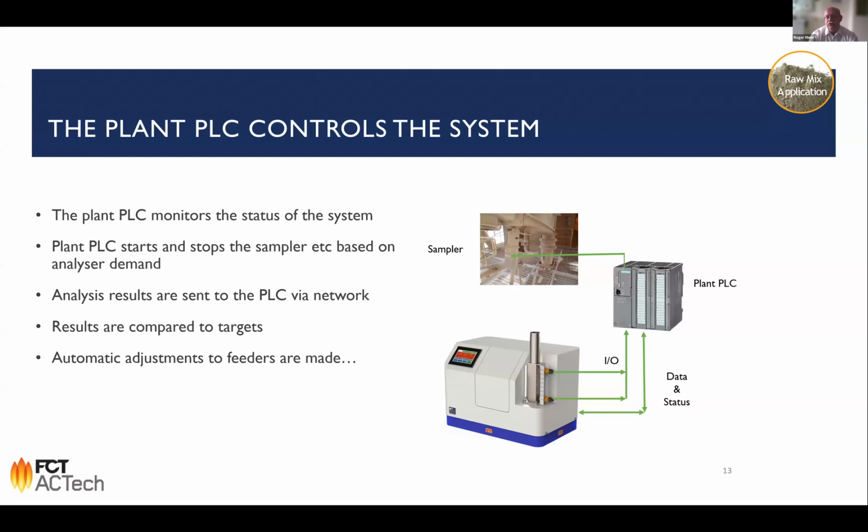The material goes into the analyzer, is analyzed, and then returned. Of course, we also have a backup sample as an option. The whole thing happens fully automatically, so there is no human interaction required. Also the start and stop happen by using the IOs from the sensors here. We always have fresh material in the analyzer. The analyzer will not run out of sample.